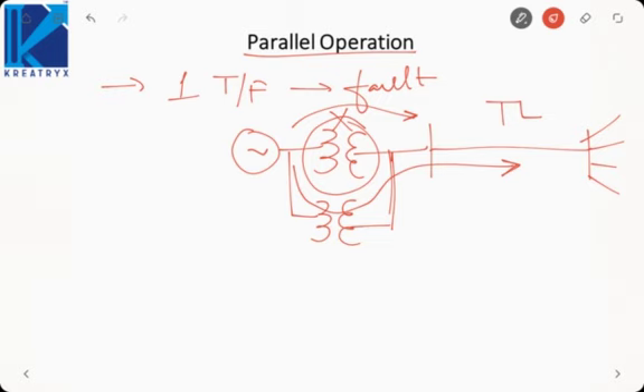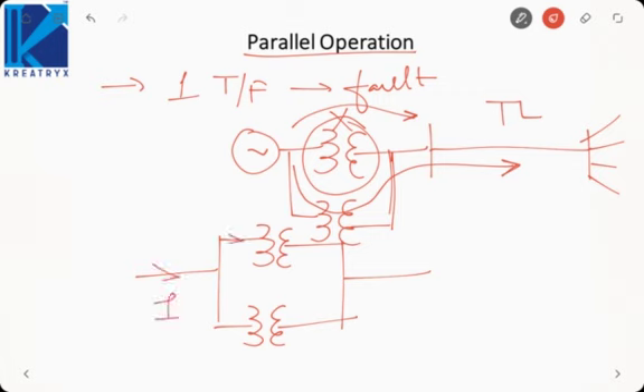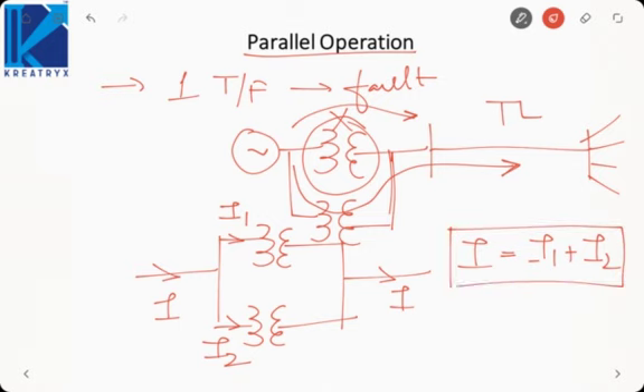Other thing is that if both are operating at the same time, then what will happen? The total current I will be the sum of I1 and I2. That means now more current can be supplied. Okay, instead of I1 or I2, now we are supplying I1 plus I2. So more current can be supplied or more load can be supplied. That is, capacity of the entire system is increased. Now we can supply more load, or the transformer has the capacity to take more load. That is the benefit of the parallel operation.